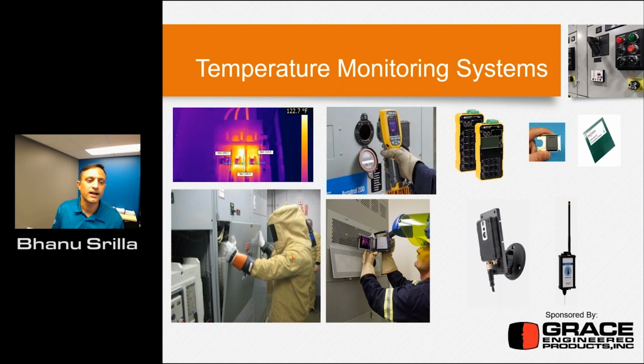You need to make sure that you follow this temperature monitoring, because on the previous slides I showed these loose connections. These loose connections can be monitored using these non-contact type devices, where you can monitor the temperature using thermography as one of the tools. But you need to also understand the pros and cons of every technology, right? So you need to understand, whenever you do a thermography program, you're not just shooting an IR camera like at the airports, what people are doing right now to monitor the temperature.